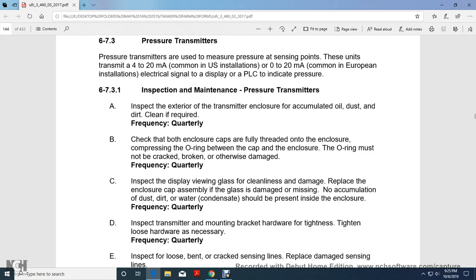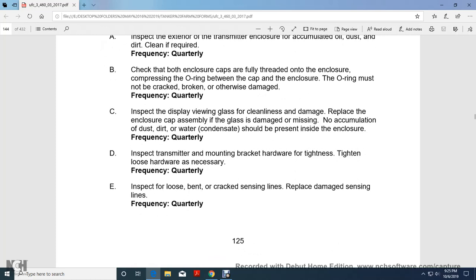The O-ring must not be cracked, broken, or otherwise damaged. Quarterly, inspect the display and viewing glass for cleanliness and damage, and replace the enclosure cap assembly if the glass is damaged or missing. There should be no accumulation of dust or dirt. Water condensation should not be present, including inside the enclosure. Inspect the transmitter mounting bracket hardware for tightness. Tighten any loose hardware if necessary.